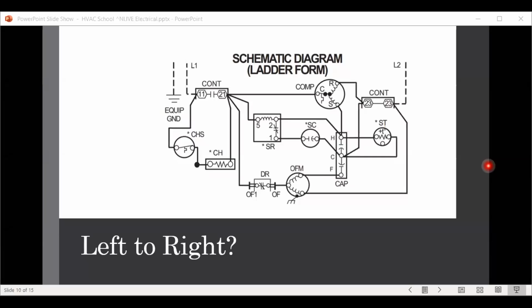Got him put in, but before I went to figure out the problem, I didn't put that thermostat on the wall because I wasn't about to blow up another thermostat. That's wise. Made sure that the boards were fused out properly, and then I just jumped it at the thermostat into cool mode and heat mode to see what was going on there. Tried to jump it into cool mode, jumped red to orange, yellow, and green, and it blew the fuse just like that. So I went in and put my popper in there and figured out it was on my reversing valve wire. So I figured out the thermostat there.